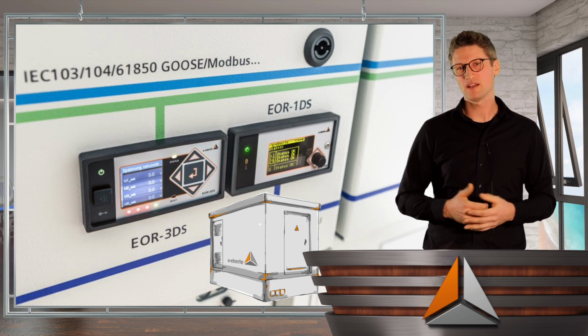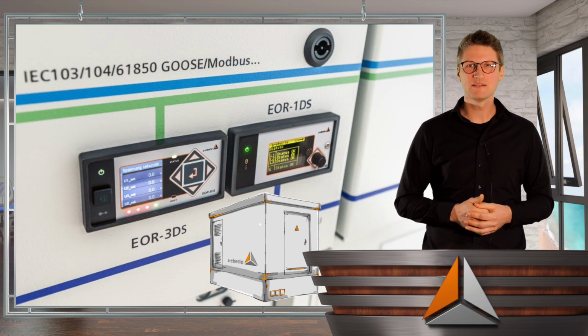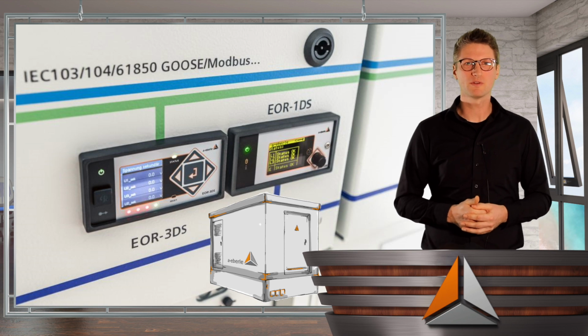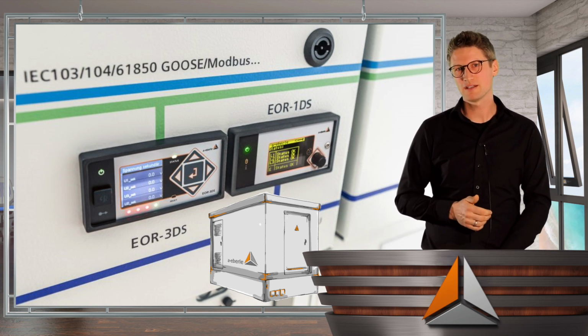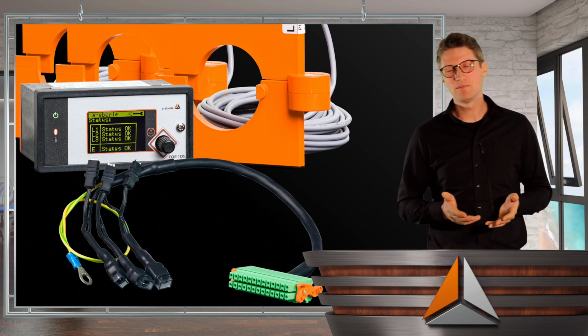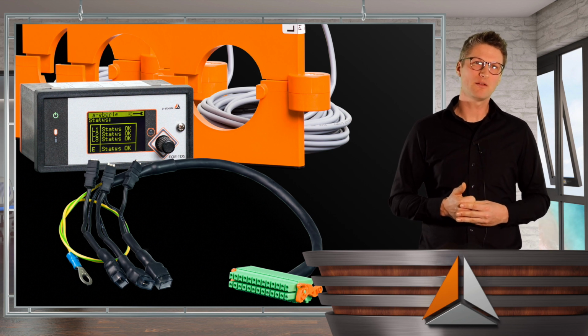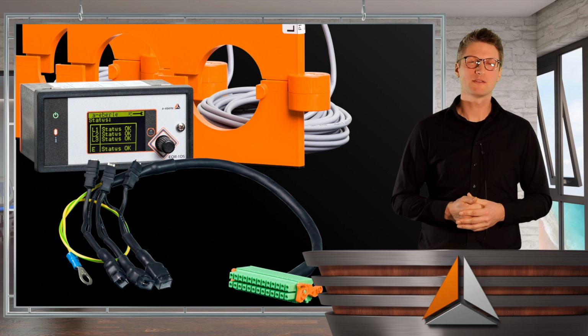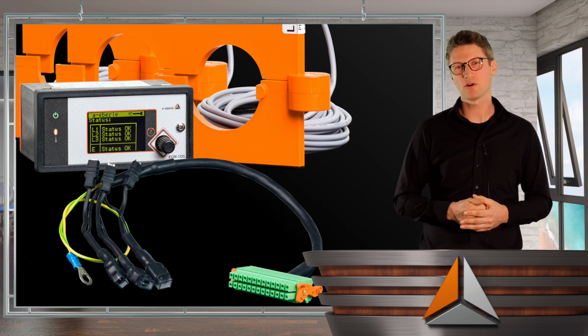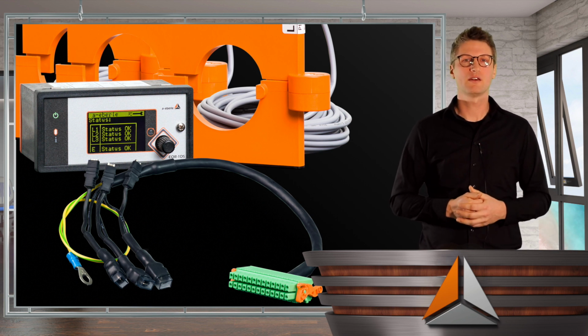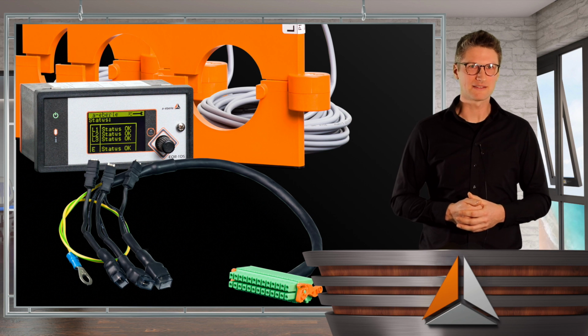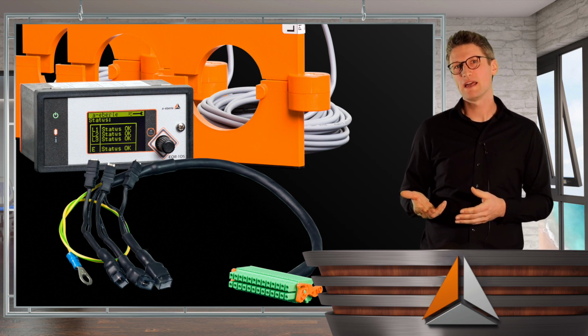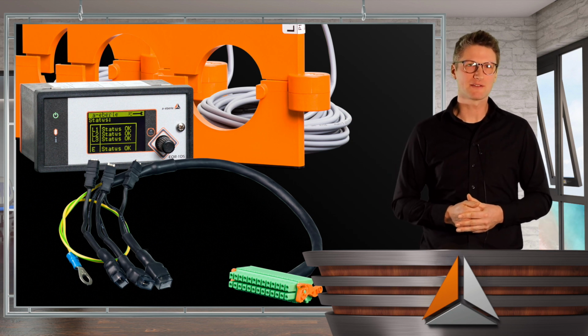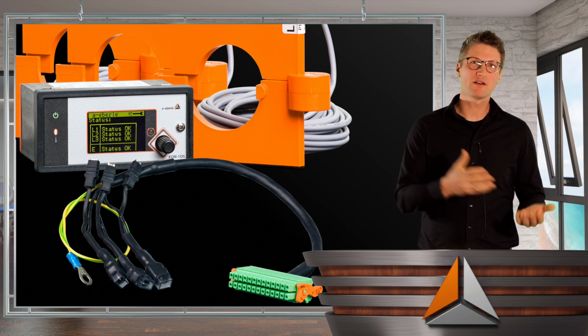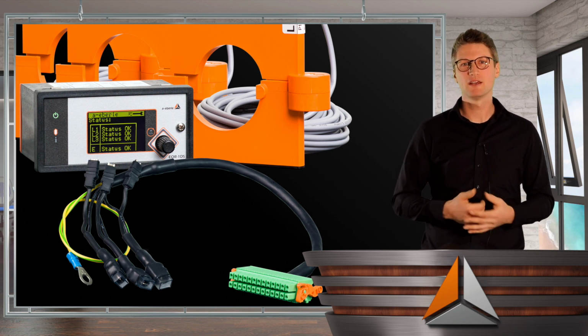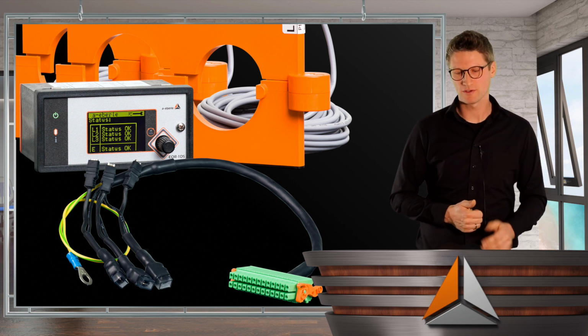And if at least an earth fault and short circuit indicator is installed, there's no communication to the central SCADA system. So staff has to go there and has to look for the direction of a fault. Our EOR1DS as a simple and cost-effective retrofit solution helps to improve the current status. So the device comes with 3 Rogowski coil sensors, and therefore you can have an undirected indication if you install it like this. On the other hand, you have the option to measure the voltage parallel to a voltage detection system like a CAPDIS or WEGA system. And then you have current measurement and voltage measurement. You have the chance to get a directed indication of earth faults and short circuits.